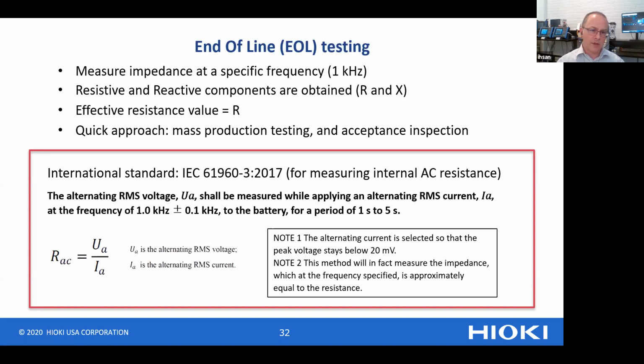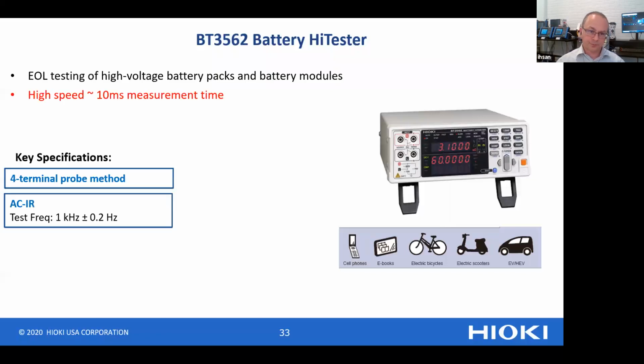The way we do this is the resistive and reactive components are obtained at 1 kilohertz, but we only take the effective resistance value, or the real component of it, R. And this follows the international standard, IEC 61960-3, for measuring internal AC resistance, which specifies a test frequency of 1 kilohertz and a measurement time of 1 second to 5 seconds. So for end-of-line testing, our main concern is high speed.